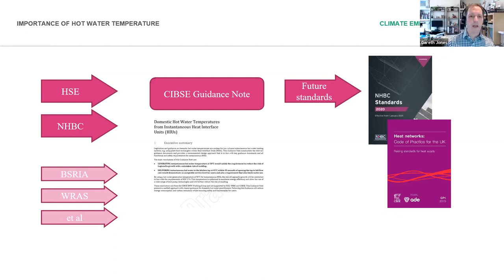Thanks, Gareth. Great. And I'll just add to that. So under CP1 2020, and this is actually also coming out from the CPC Domestic Hot Water Group, there is a requirement that you are able to generate hot water at 50 degrees. Based on conversations with HSE, it's really important to emphasize this is for the specific use case, but what we're talking about here is effectively they're similar to point of use devices, and they're considered to be a low risk of Legionella from that perspective. So low risk systems, and when you're looking at balancing, 50 degrees is sufficient as a generation.